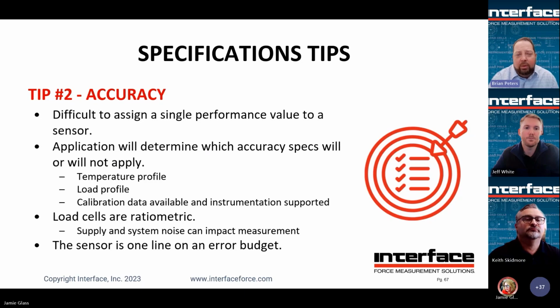So load cells are ratiometric. We mentioned this earlier. Pay close attention to the quality of the excitation going to that sensor, because any noise coming in on that excitation side is going to show up in your measurement signal. So pay close attention to that. And again, in summary, the sensor is just one line. We spend a lot of time on sensor specs, zooming in on the sensor. Now you've got to look at everything else attached to it. Next one.